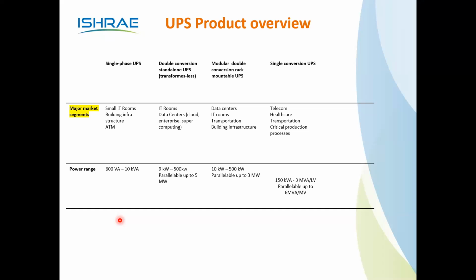Now, say just for example, the current load is say 200 kVA, and it may go up in future, say 300 or 400 kVA UPS. In conventional UPS, they are going for UPS systems of higher capacity from day one, considering the future expansion. So here the main block is capex investment. The capex has been blocked from day one, even though the load is only 100 kilowatt or 200 kilowatt.